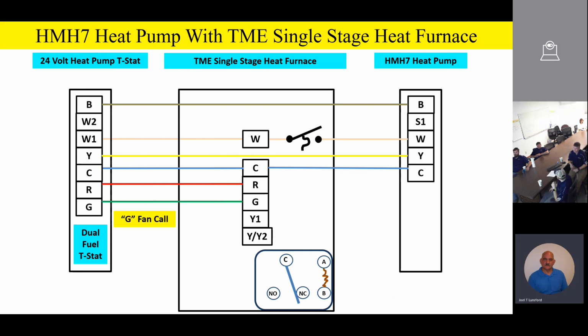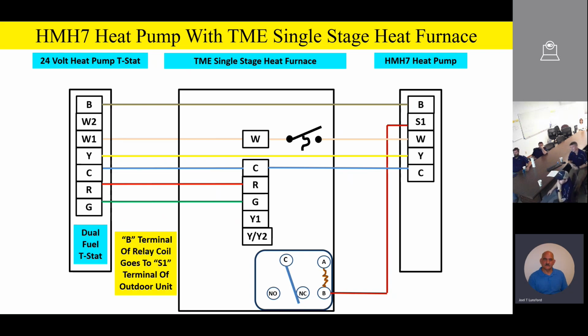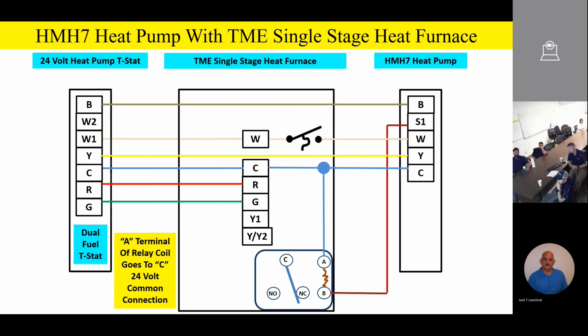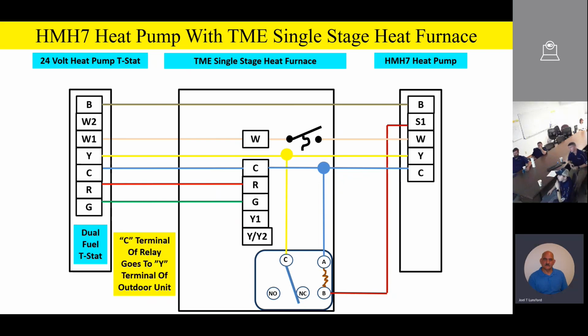And G terminal is 24-volt fan call. Now, on the relay itself, we're going to notice it's pretty standard like we did before. One side of the coil goes to S1. The other side of the coil goes to the common terminal so we can complete the coil circuit on the relay. The common terminal on the switching contactor will go to Y terminal, just like we had before. So anytime we have a compressor call on Y, we'll feed power to the relay switching contacts.